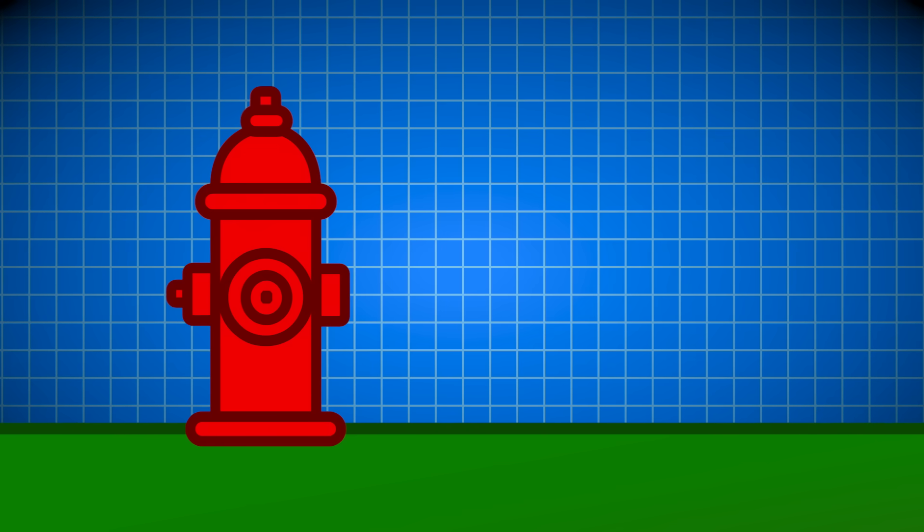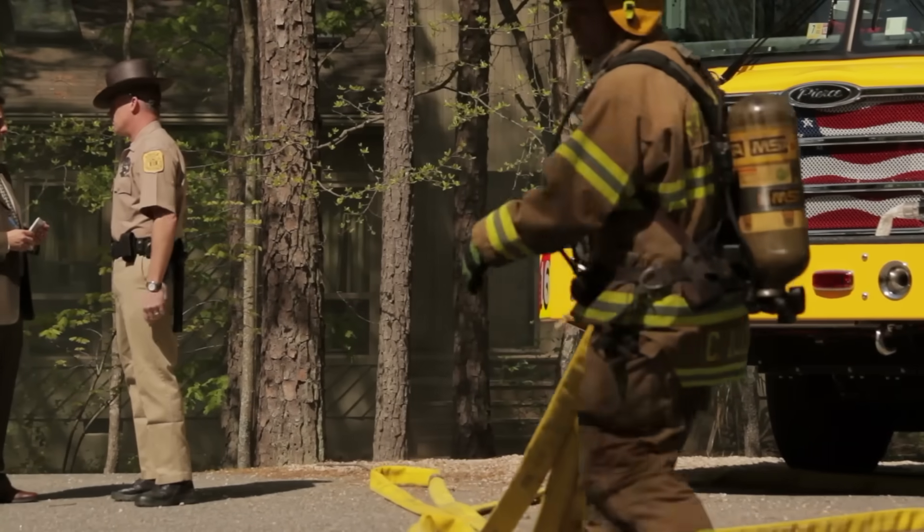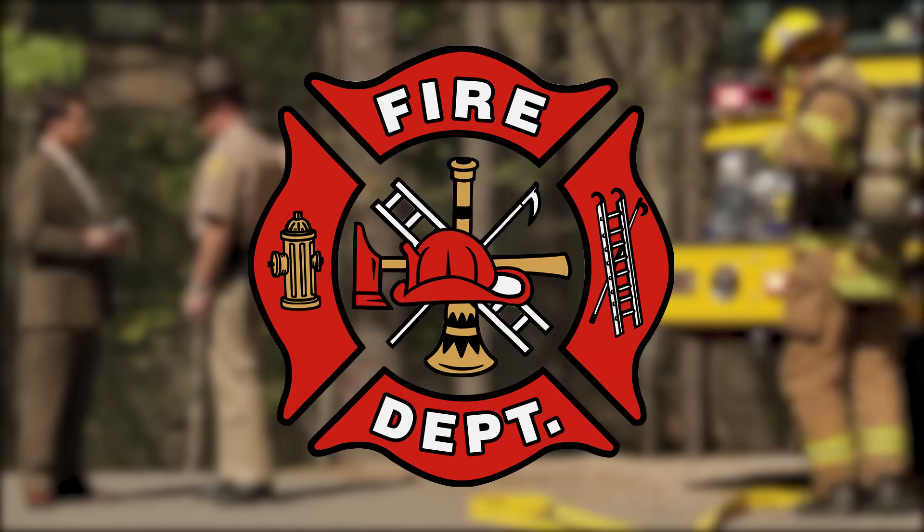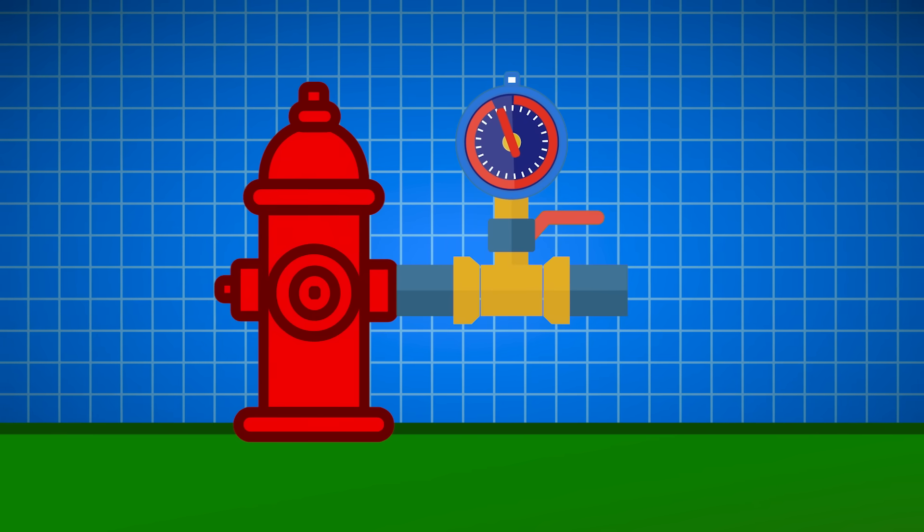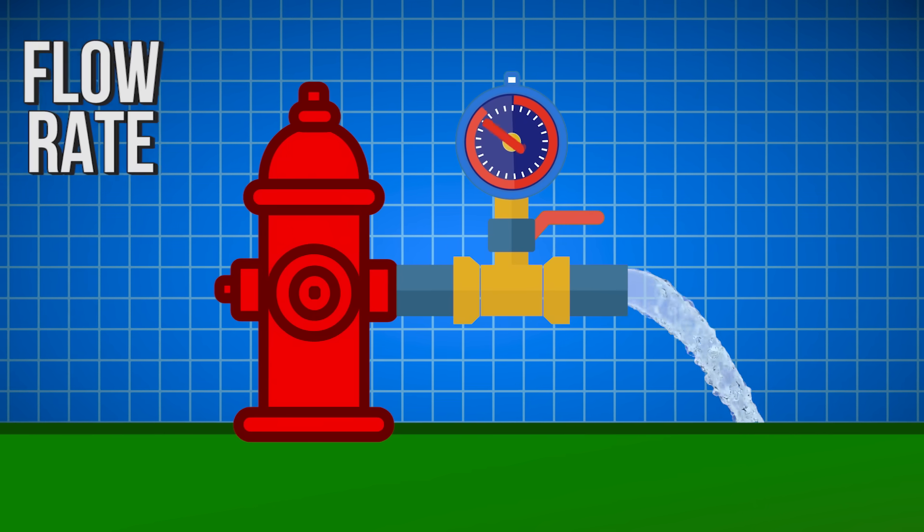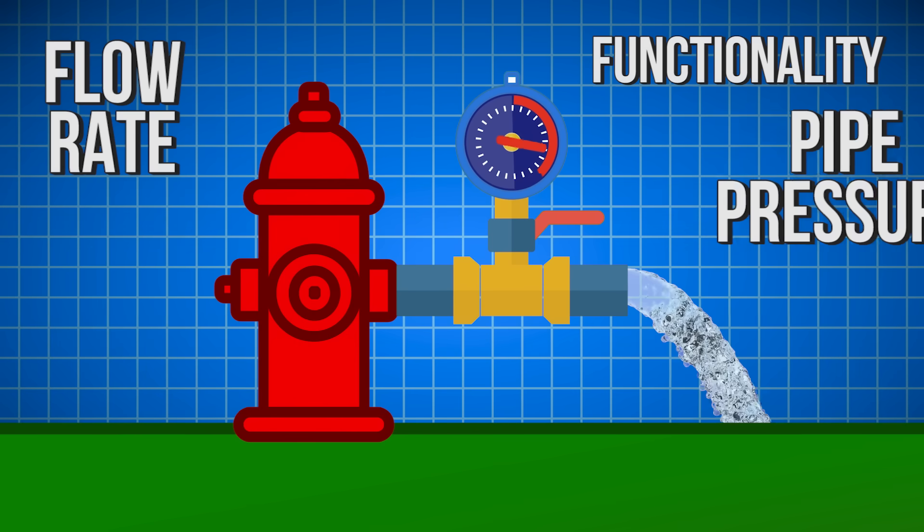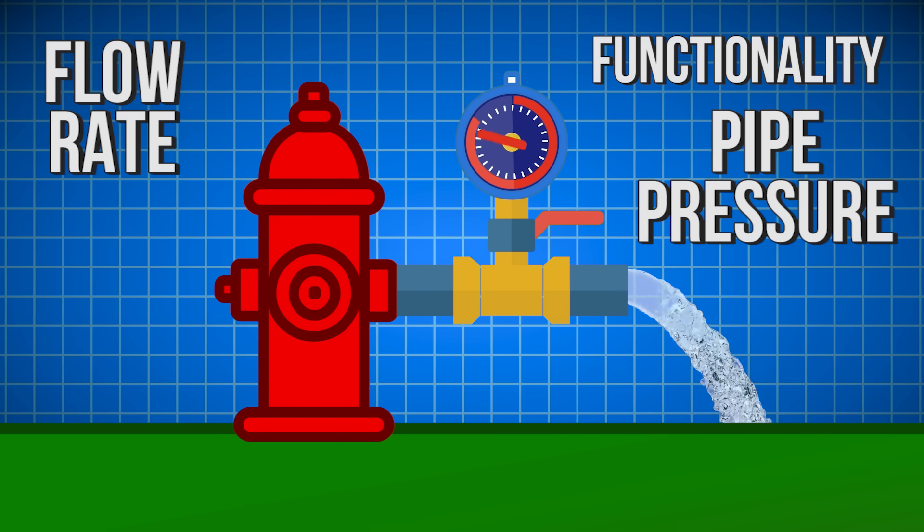Some hydrants are rarely used, which is obviously preferable, but they still have to remain at the ready. This importance means that the fire marshal and other authorities perform regular inspections of hydrants, usually by attaching a pressure gauge and measuring the flow of water. Inspectors will check flow rate, valve functionality, and pressure in the pipe, both before and during the flow.